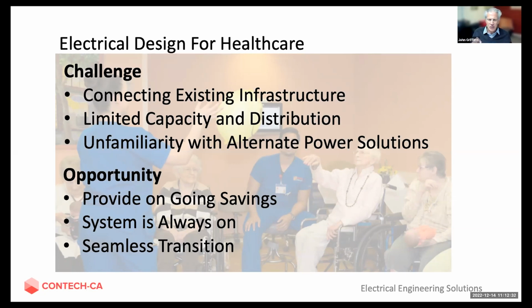And then there's seamless transition. A small point, but when evaluating options, a diesel generator or other distributed source takes 10 seconds up to a couple minutes to come back on. This meets code, and the intent is to keep temperatures and the building safe, but in terms of operating a facility that can be quite disruptive - resetting technology, air handling units, fire smoke dampers and doors. I think that's a value of delivering a sustainable microgrid.